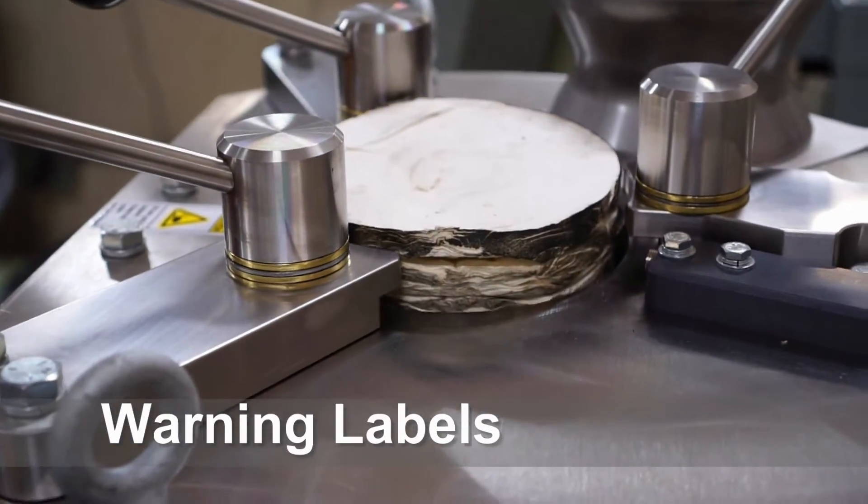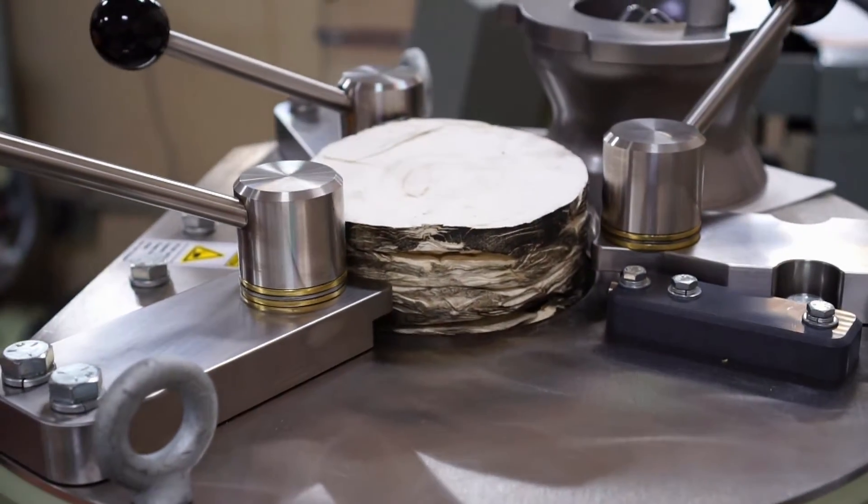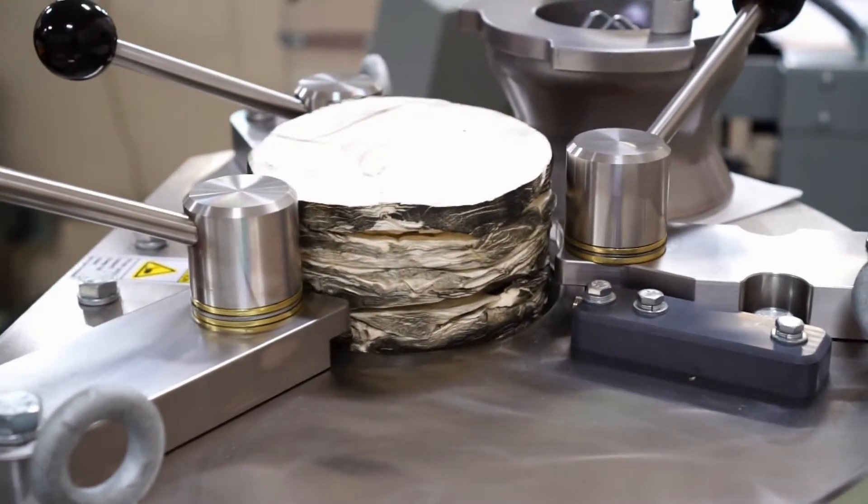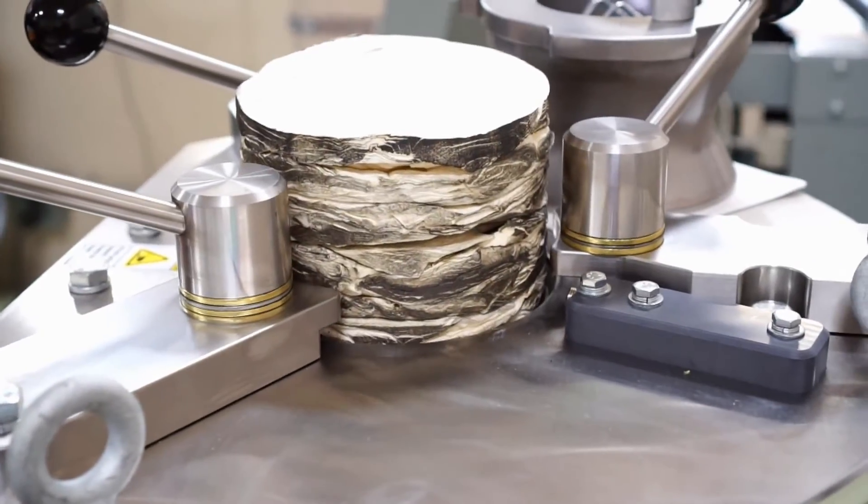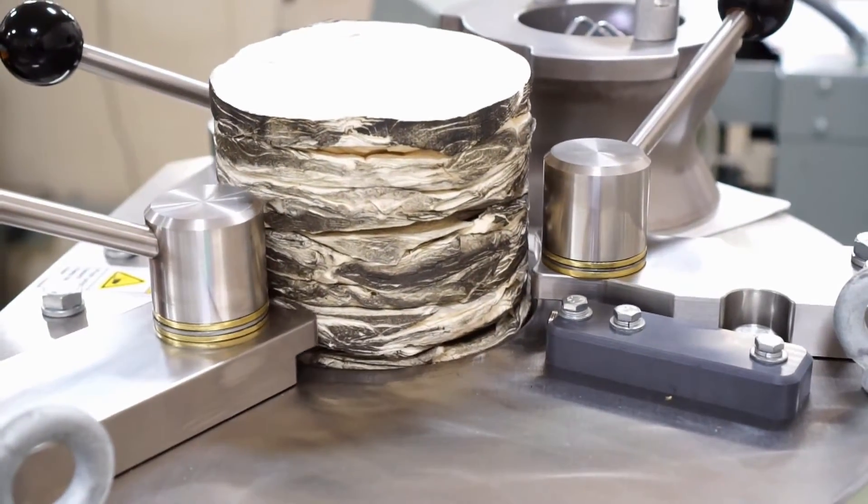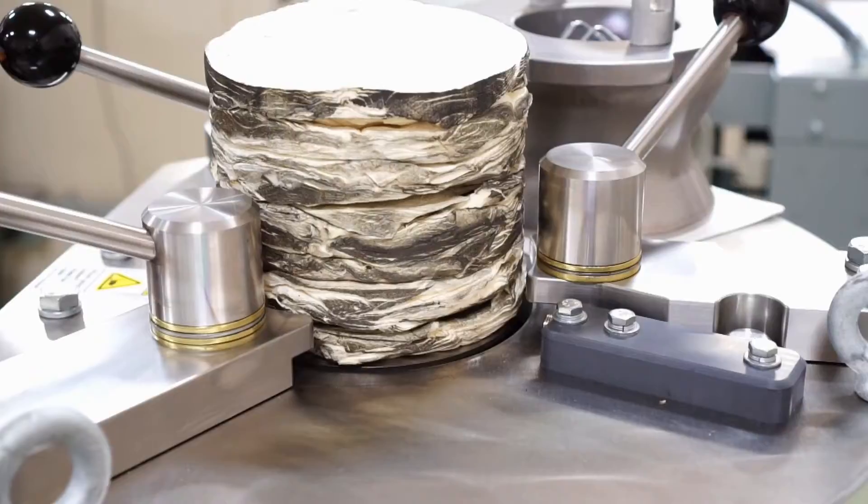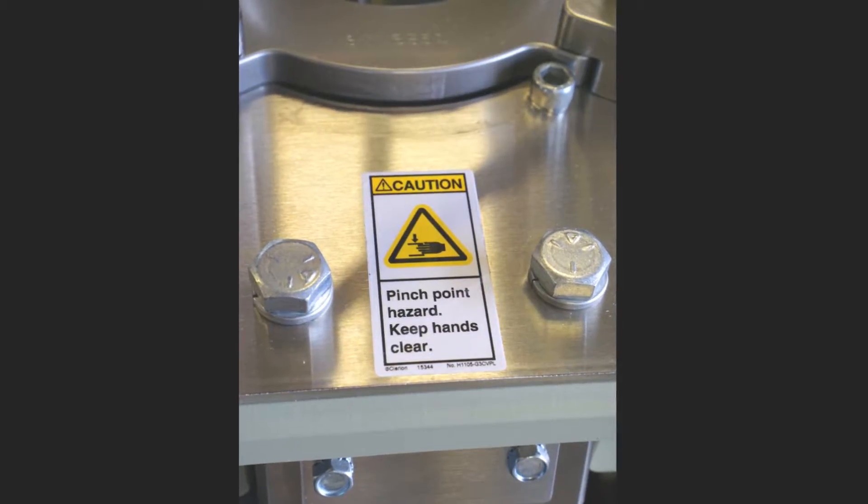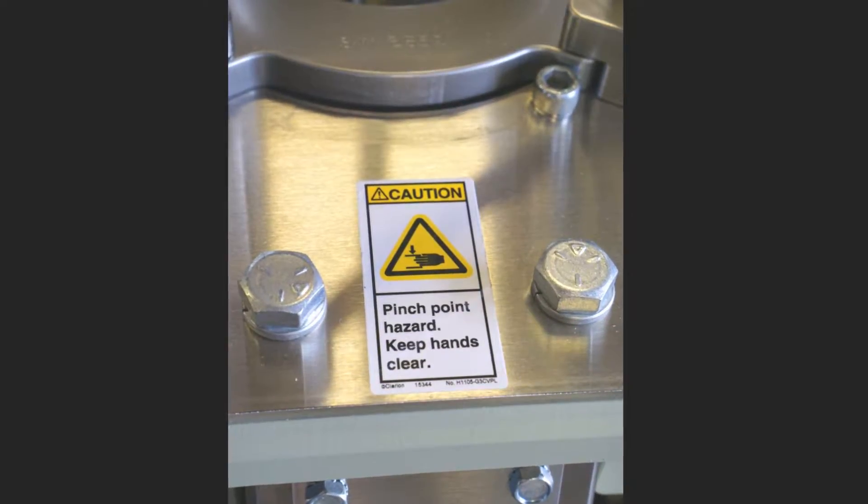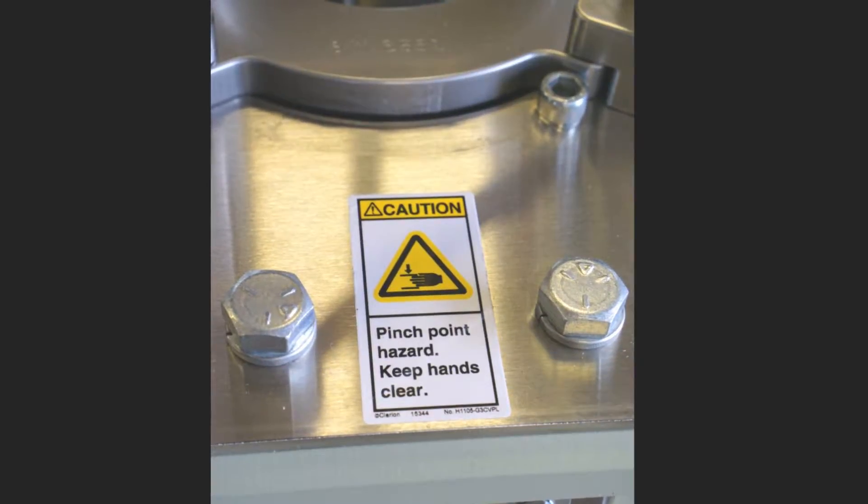As the specimen is extruded and it's rising relative to the stationary parts of the machine, a pinch point is created between the specimen and the top plate of the machine. Injury to the operator can result if the operator's fingers are placed into the top opening before the specimen begins to emerge. A label warns of this danger.